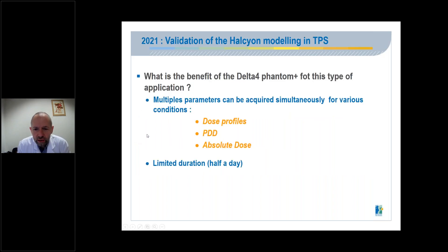In 2021, another application was the validation of the Halcyon modeling in TPS. What is the benefit of the Delta4 Phantom Plus for this type of application? First, multiple parameters can be acquired simultaneously for various conditions, such as dose profiles, PDD, absolute dose. Then, the time required for the application is limited, about half a day.